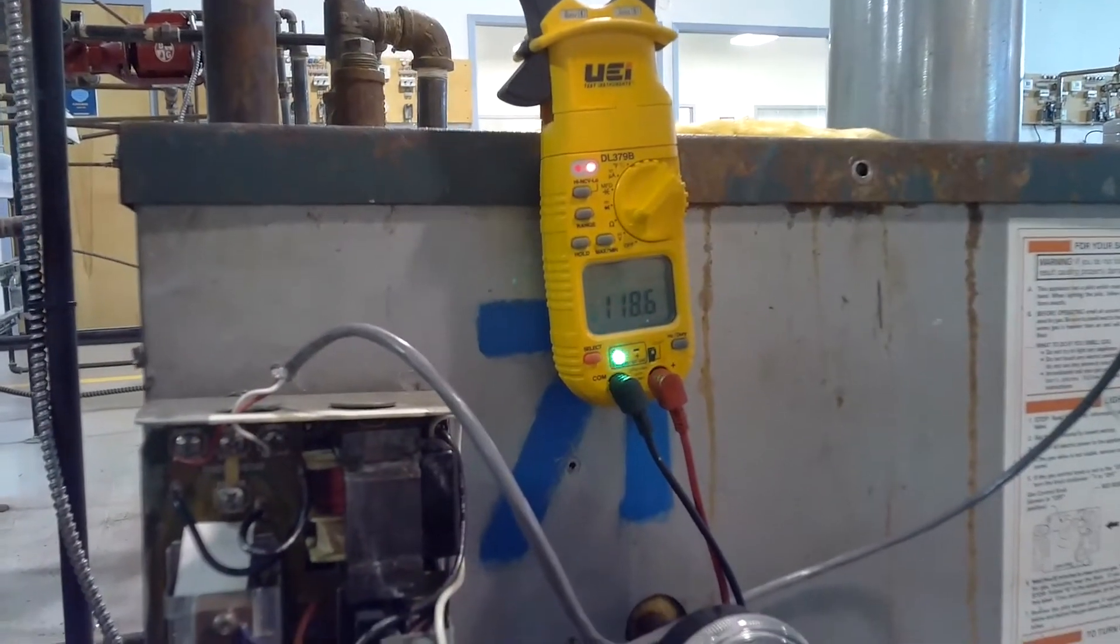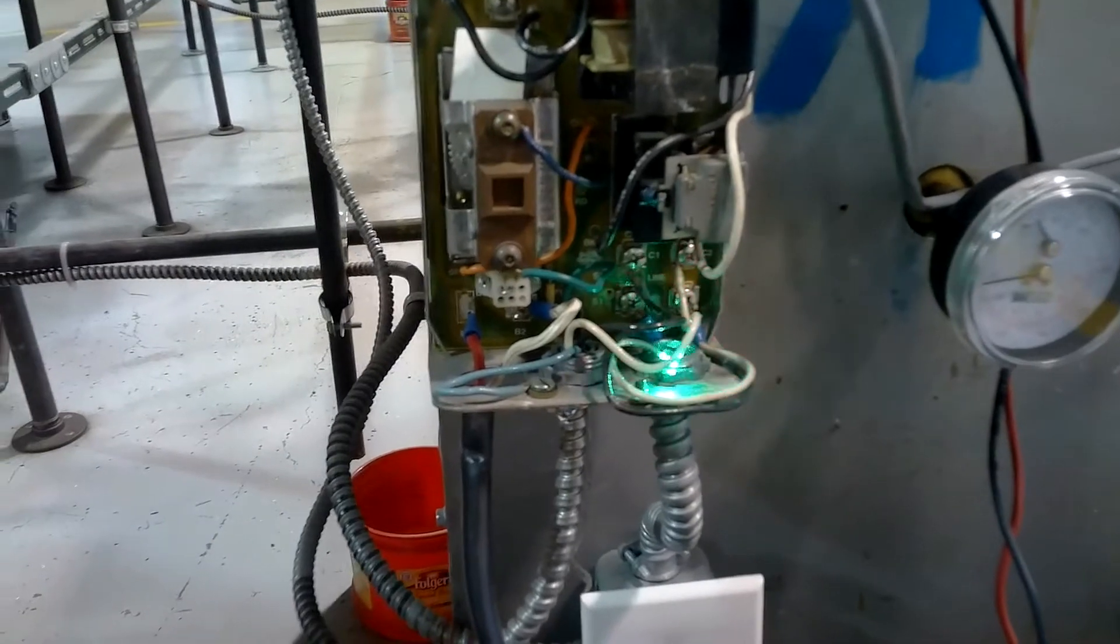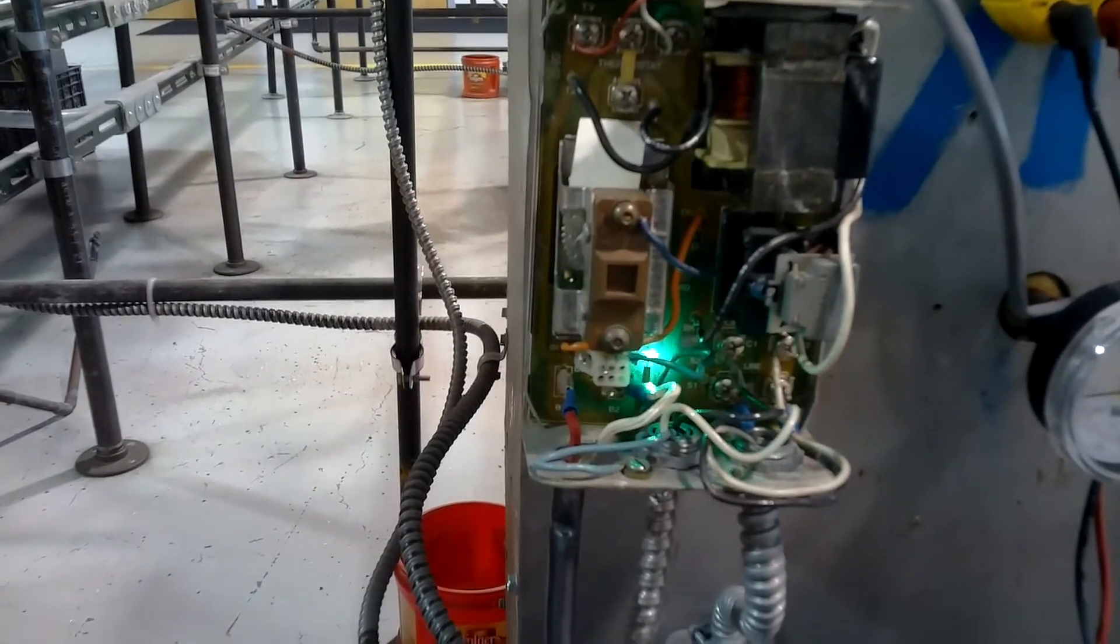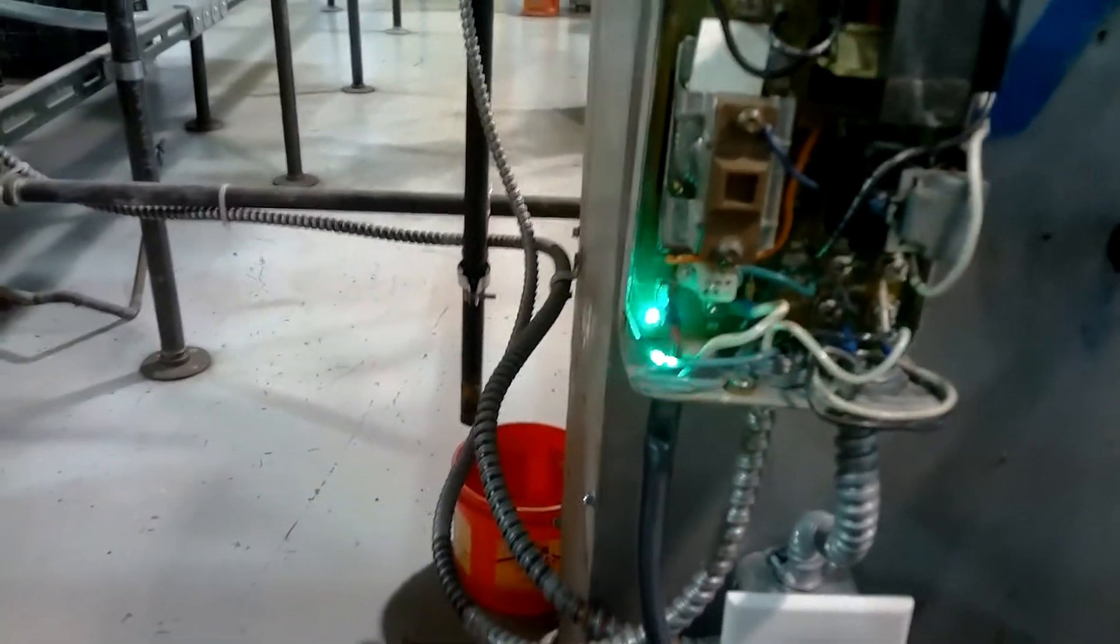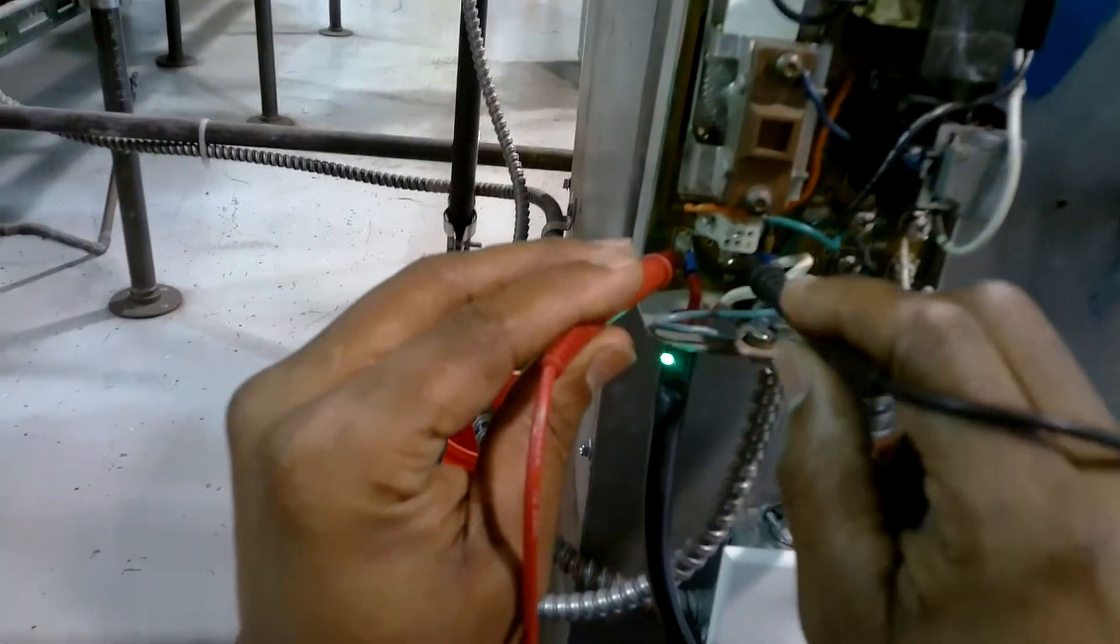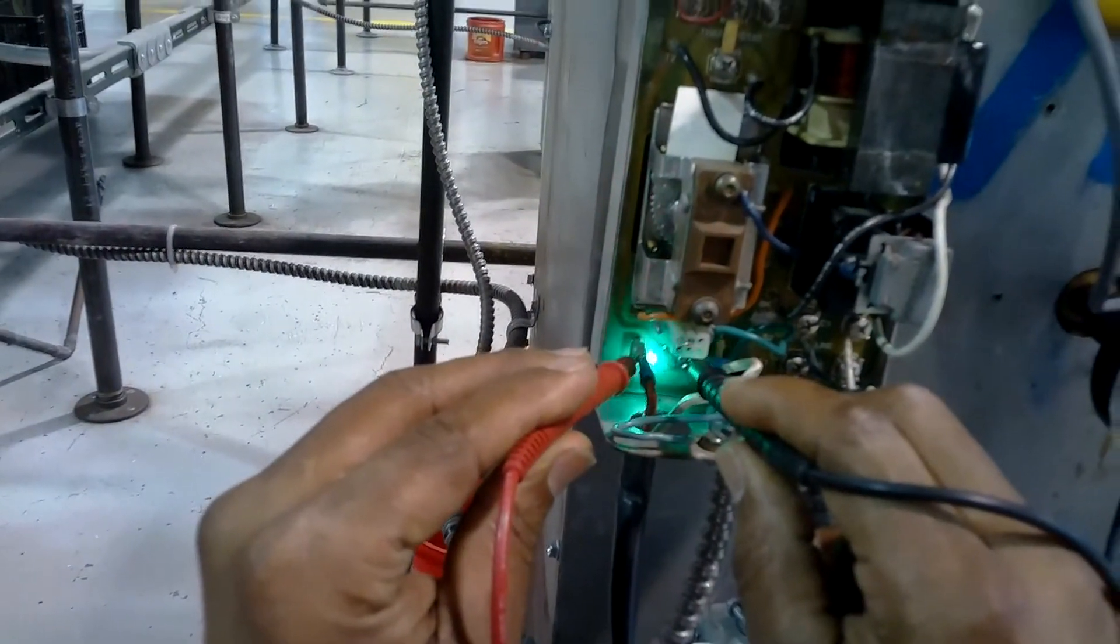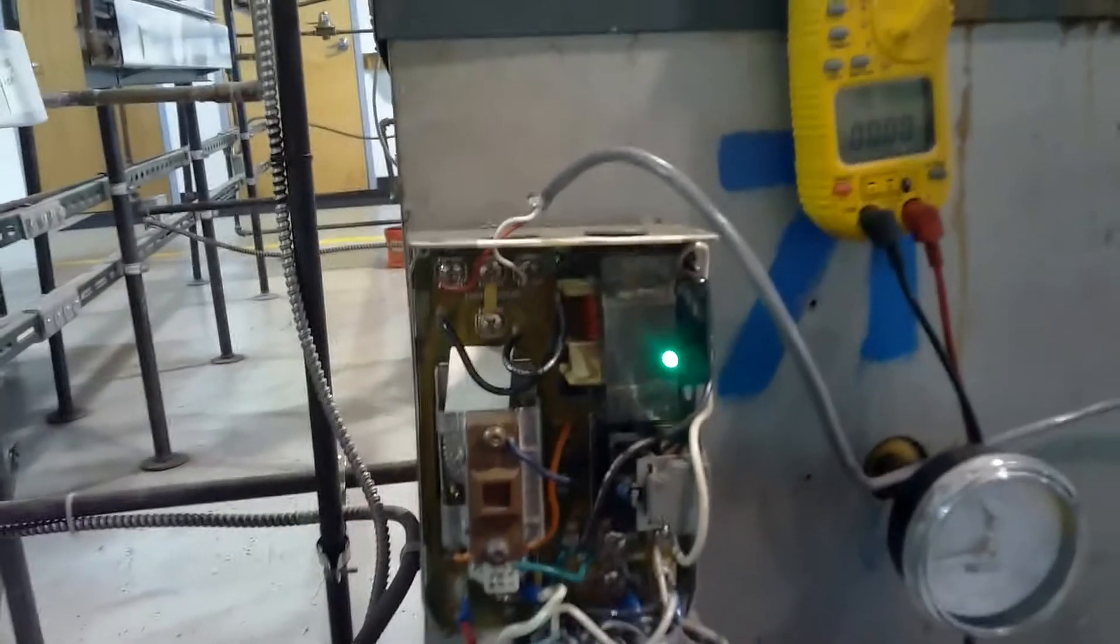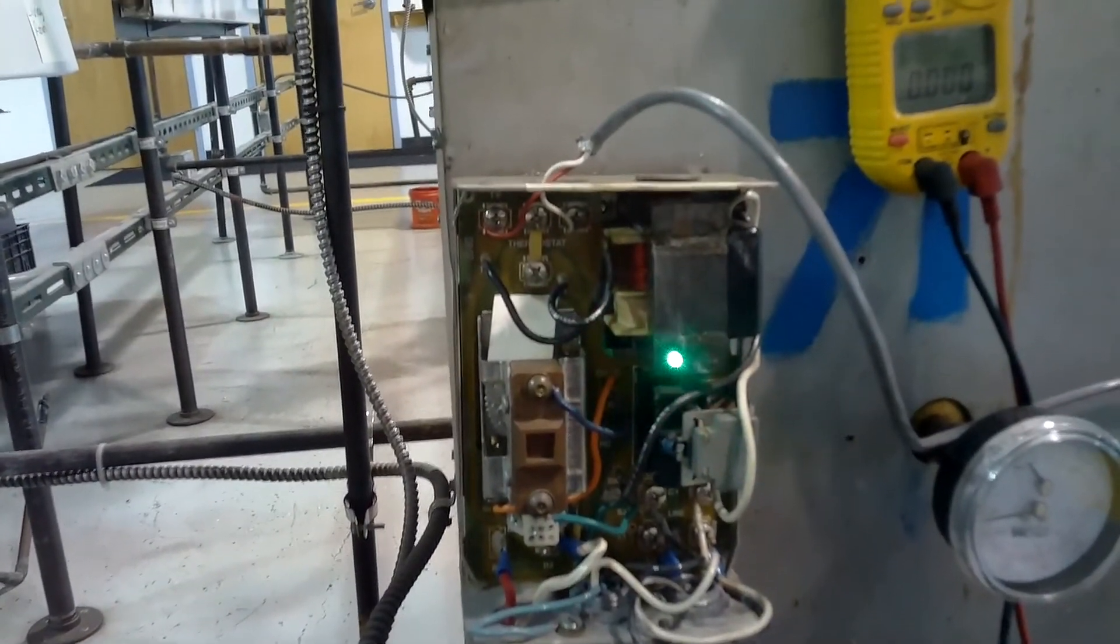I have 118 volts. Now I'm going to check 24 volts coming out of my aquastat going to my gas valve at B1 and B2. 23 volts. So now I can also check power coming out of my limit.